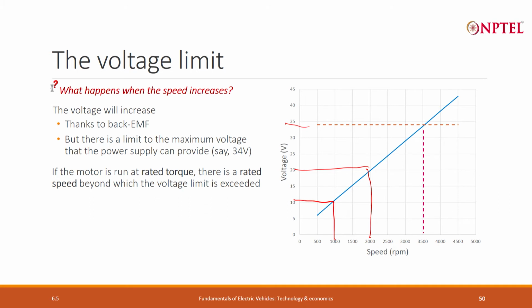All of this I am doing when I am supplying 160 amperes and I am trying to get the full torque of 22 Newton meter. Under that condition I am doing this experiment.